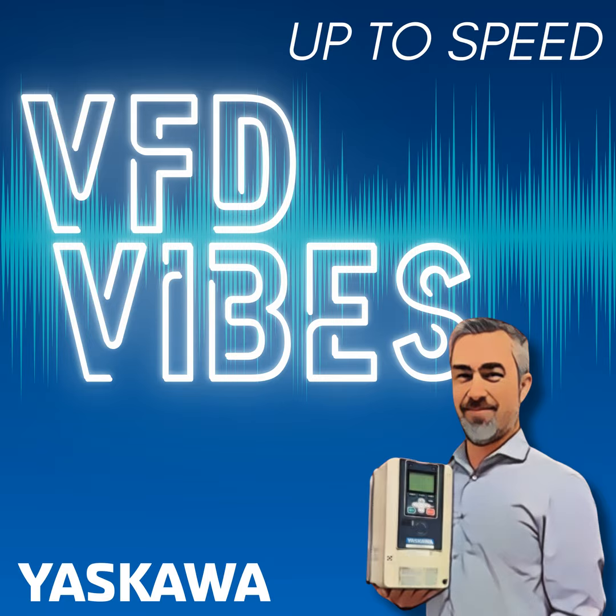So line reactors tend to help with the harmonic currents thrown back on the line from the drive, but they also tend to protect the drive from line imbalance and from noise that might be on the incoming line. The only exception to that would be a drive like the U1000. The U1000 is a special thing. It's a direct AC to AC converter. Those are a little bit special in terms of what you do on the front end. But if you're talking about a standard drive, like a GA800.